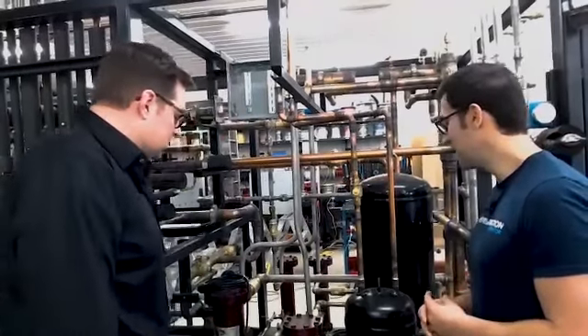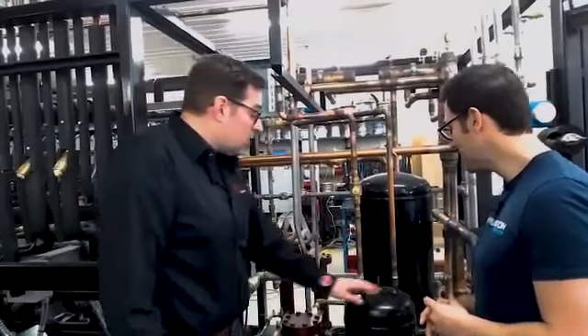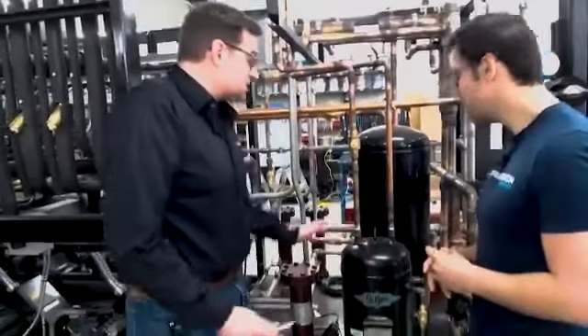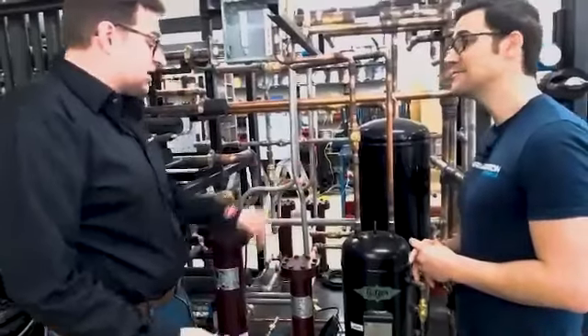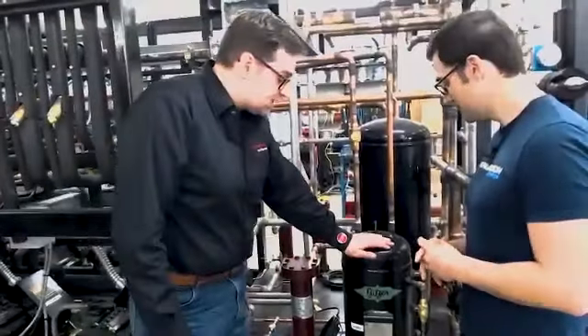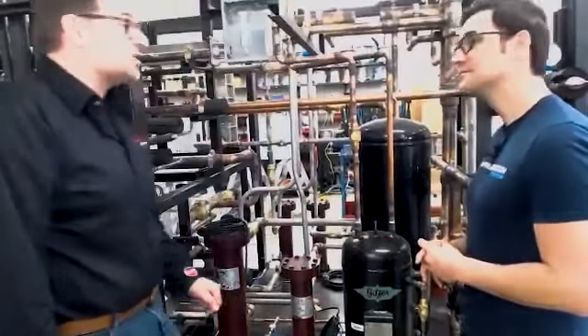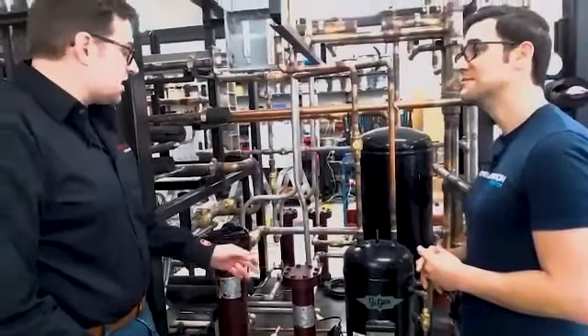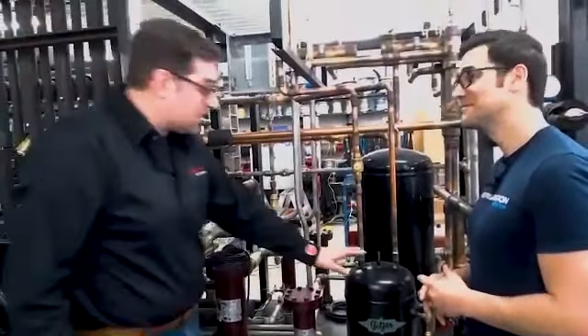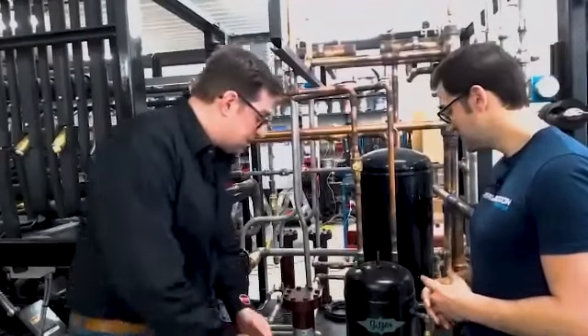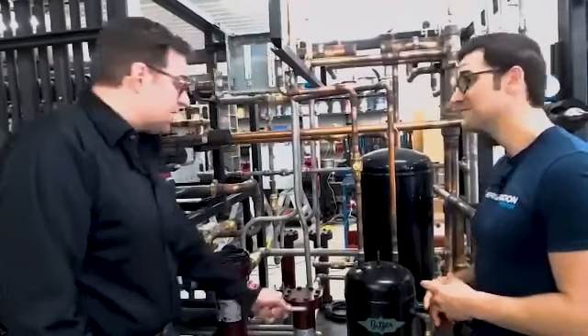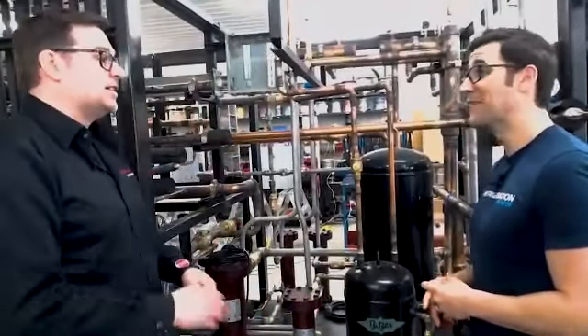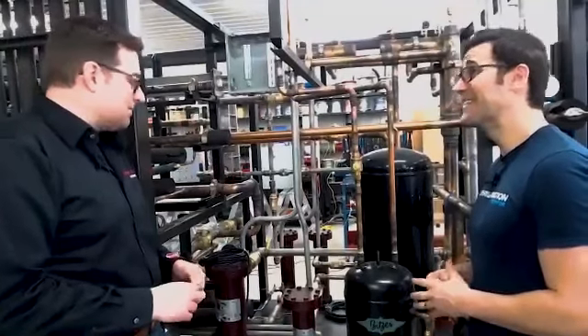It looks really cool. Oil receivers for us come in all shapes and sizes. We're doing one right now with a 60 liter, this one's a 29 liter, and we go as small as 7 liters. With high pressure designs, small minis, you won't even have an oil reservoir — you could have a piece of 3/4 inch stainless steel pipe with a continuous feed.